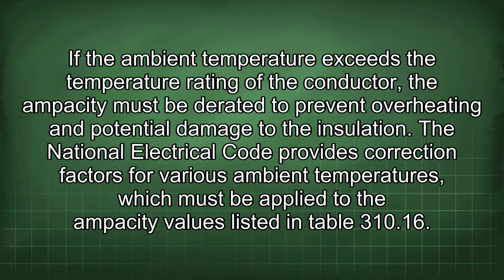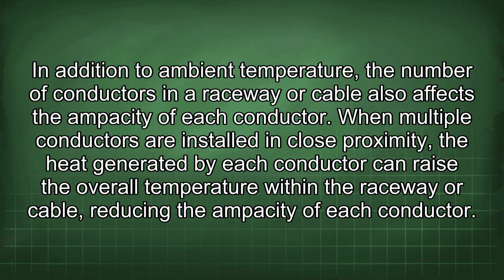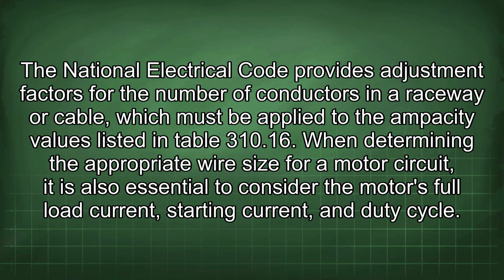In addition to ambient temperature, the number of conductors in a raceway or cable also affects the ampacity of each conductor. When multiple conductors are installed in close proximity, the heat generated by each conductor can raise the overall temperature within the raceway or cable, reducing the ampacity of each conductor. The National Electrical Code provides adjustment factors for the number of conductors in a raceway or cable, which must be applied to the ampacity values listed in Table 310.16.